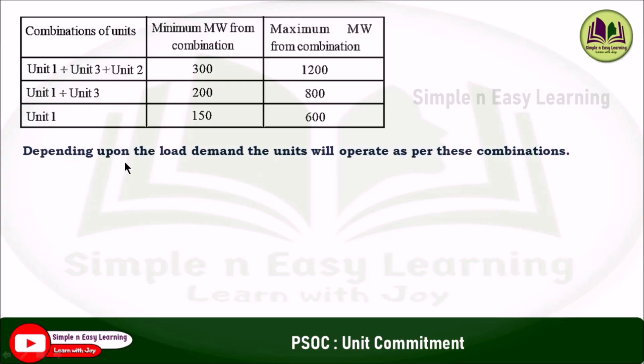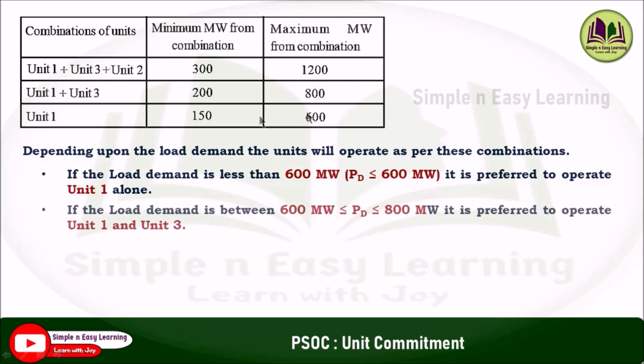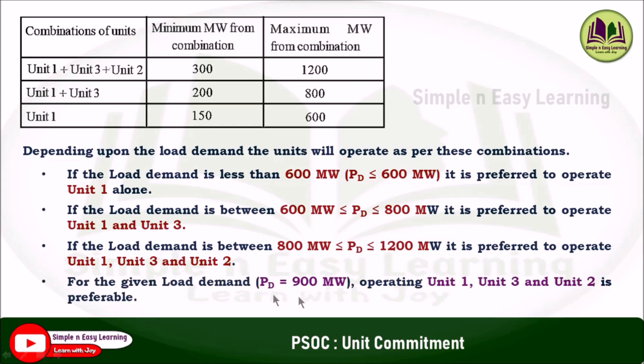Using these combinations, we can conclude: if load demand is less than 600 MW, operate unit 1 alone; if load is between 600 and 800 MW, use unit 1 and unit 3; if load is between 800 and 1200 MW, operate unit 1, unit 3, and unit 2 together. Since the given power demand PD is 900 MW, operating units 1, 3, and 2 together is preferable.